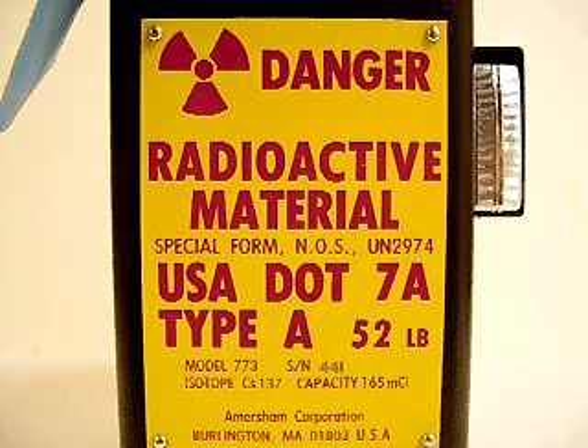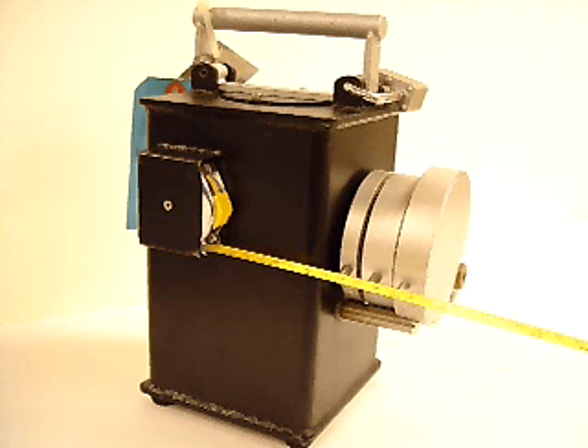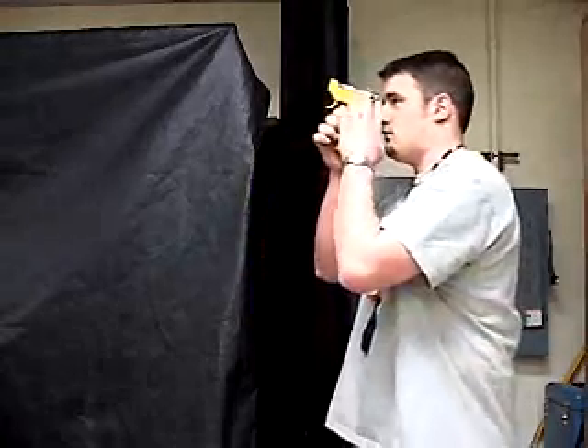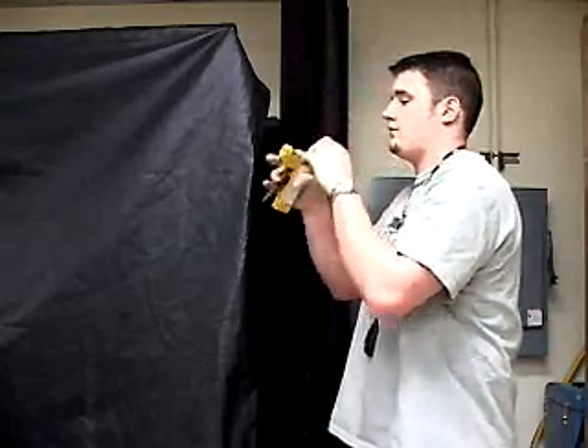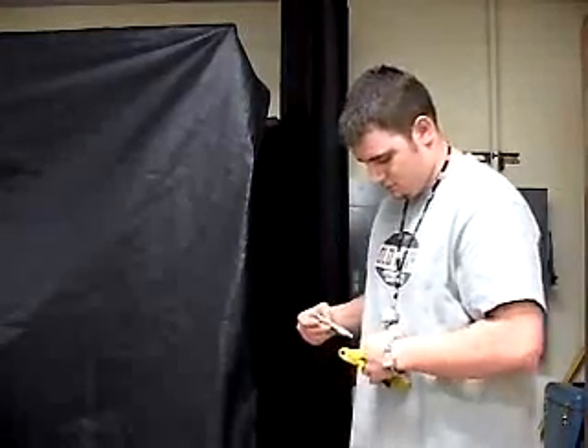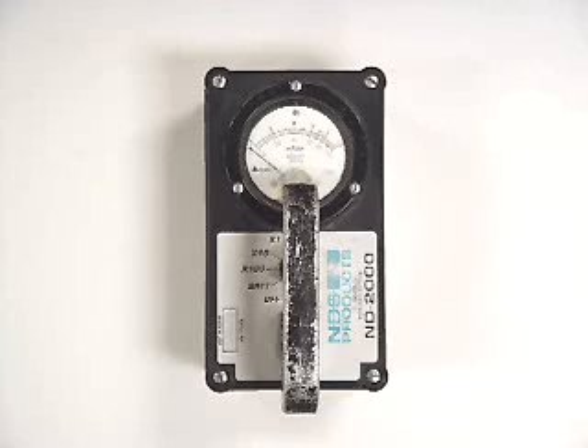A 104 millicurie cesium-137 source contained in a calibration unit will be used for the demonstration. When conducting radiographic operations, all personnel involved in the radiographic activities must, as a minimum, wear a pocket dosimeter and a personal dosimeter. In addition, the technician must have an operable and calibrated survey instrument.